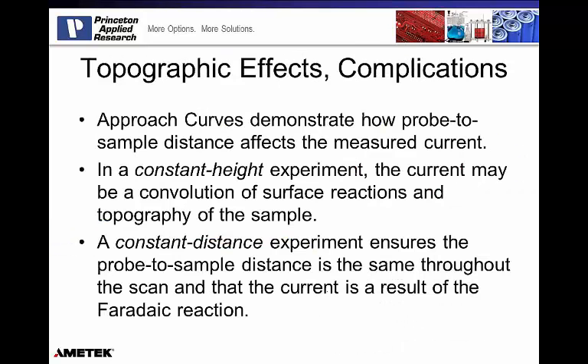So topographic effects and complications. Approach curves: if we think about this, you saw the asymptotic relationship of current to probe to sample distance, and not just saw it, we quantified that in an approach curve. And so you can see the probe to sample distance really impacts, because we want to operate in that high differential area, so that probe to sample distance really impacts the measurement in that region.